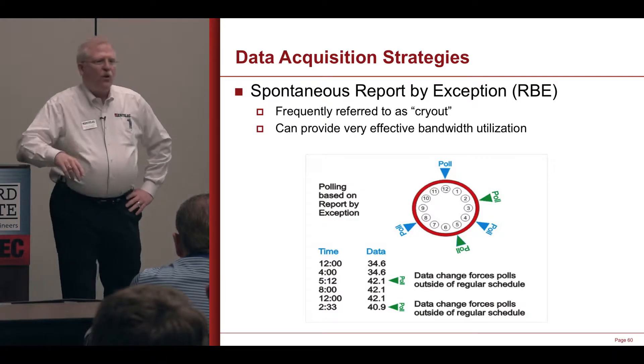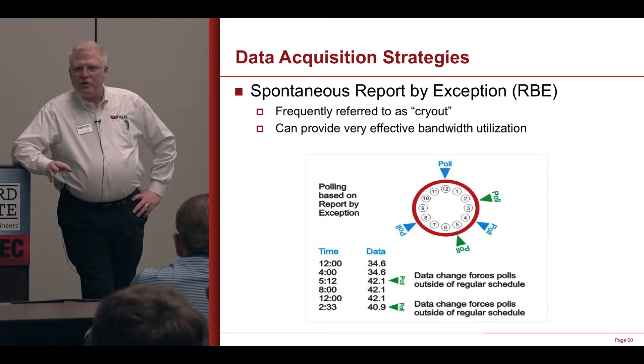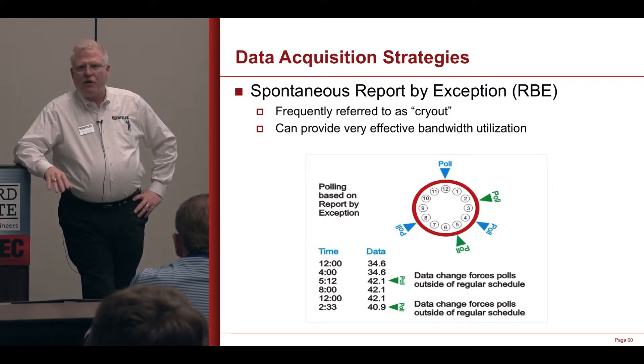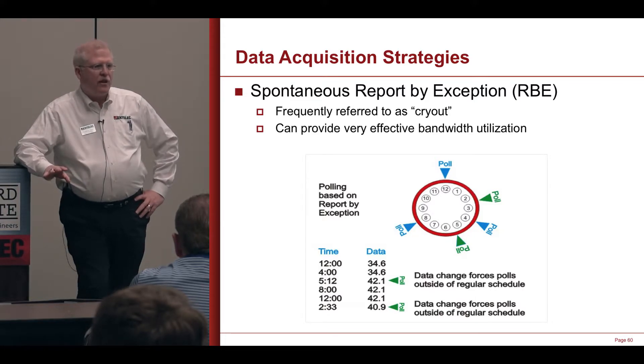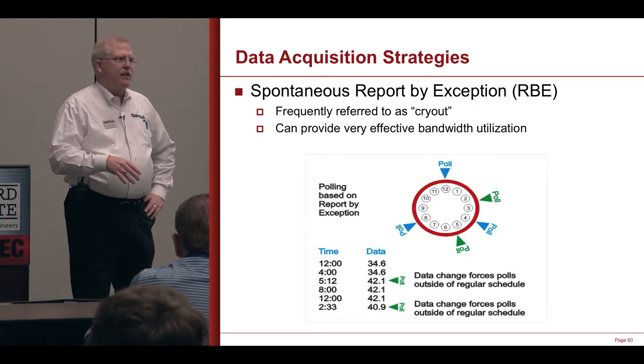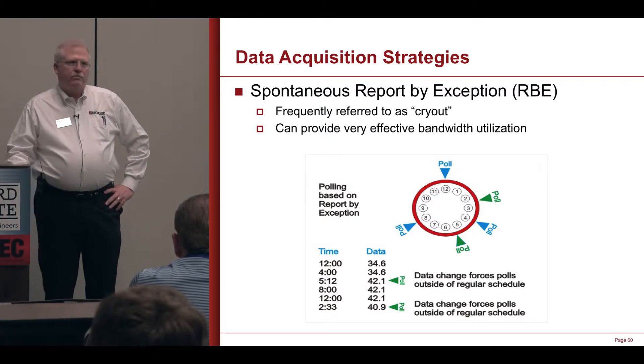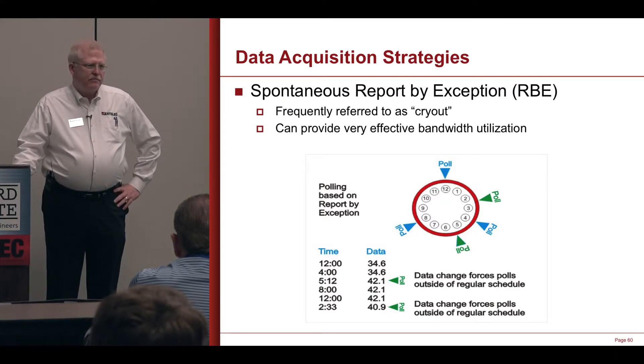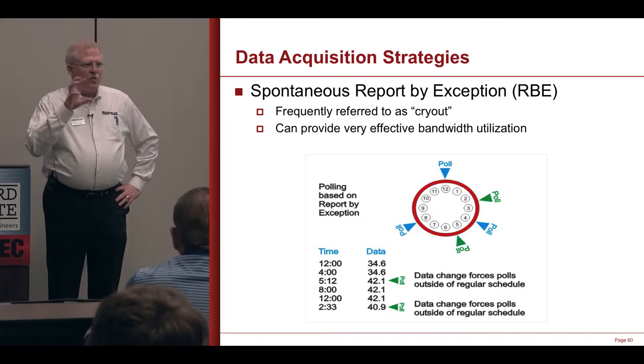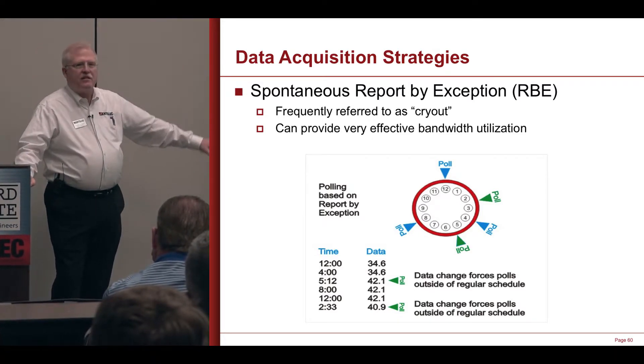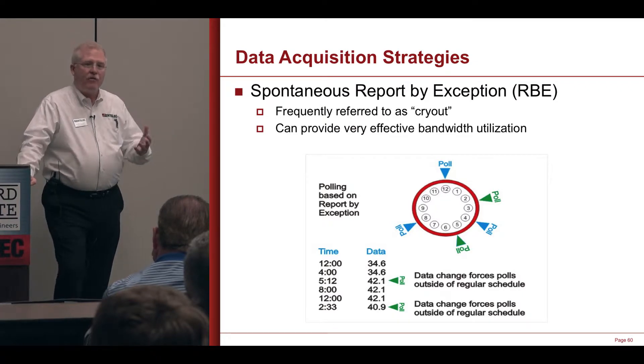We are becoming more and more interested in rich data, because we're starting to use SCADA data for analytics. Historically we've just used SCADA data for operations and measurement, but now we want to use it for analytics, and when I'm using it for analytics, I want rich data — I want data logs, I want something every 300 milliseconds. That is a different requirement for communications than what we've historically seen, so these report by exception protocols are very valuable.